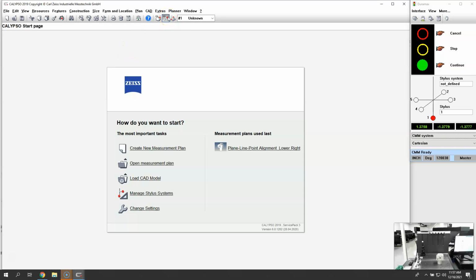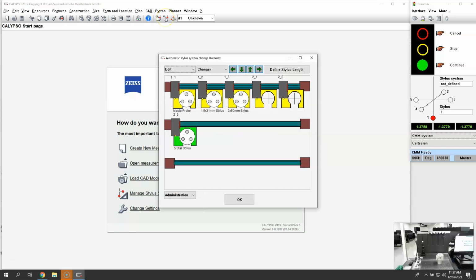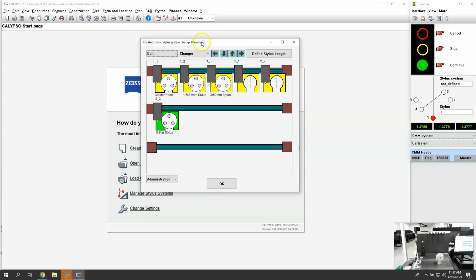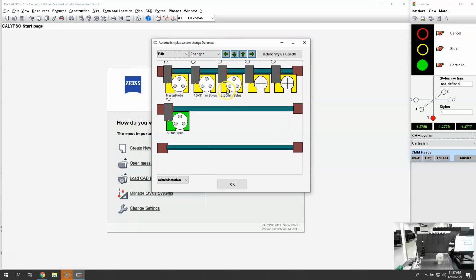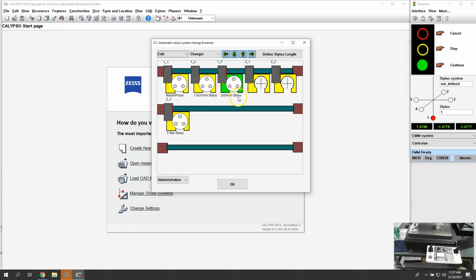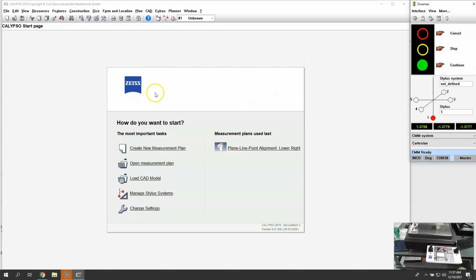Alright, so we'll come up here to CNC Stylus System Change. It's a little A icon underneath the Extras pull down. This window will open up. We do have to be very specific about the clicks here. For starters, we will look down on the controller and make sure our speed knob is closed all the way down. We are about to move the machine automatically, and it does not give you a warning. Secondly, on the computer screen, we will left click to highlight 3 by 50 millimeter stylus in green, and then we'll right click and we'll say load stylus system from holder.